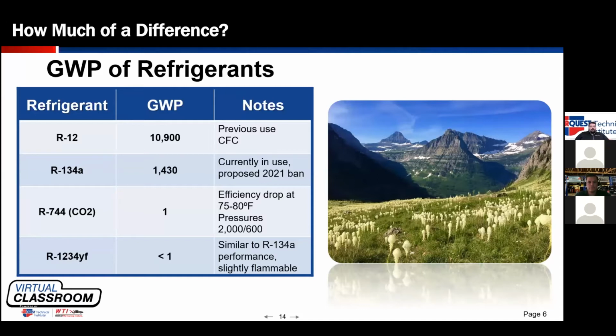A GWP of 1430. What global warming potential means is, with CO2 as the baseline, CO2 has a GWP of 1. A refrigerant that has a GWP of 1430 means that it is 1430 times more likely to contribute to global warming than CO2. So you can see from this chart, we moved from a refrigerant that was 10,900 times more likely to contribute to global warming to a refrigerant that was 1430 times more likely. That's a big step.